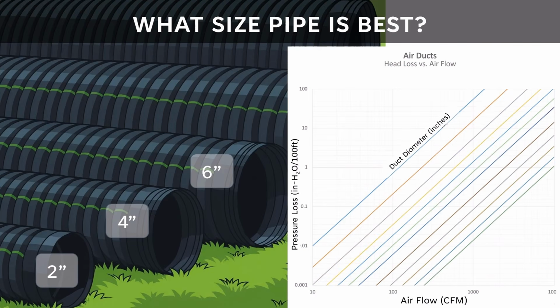Here's a graph. On the bottom axis we have the amount of airflow. On the vertical axis we have pressure loss or friction. As the pipe diameters decrease, the pressure drop increases exponentially. So 4-inch pipe brings a good balance between heat transfer and the cost to move air through it.